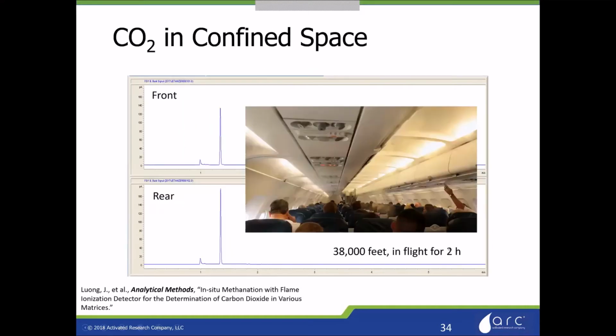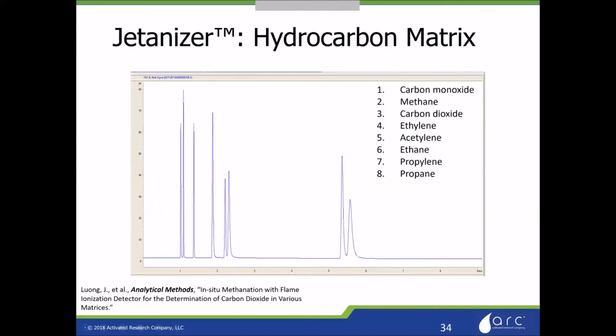And I will mention about the backflush, there is a little bit of back pressure from the Jetanizer, and you can use that to your advantage to drop the inlet pressure and force flow to go backwards through your column to flush out any heavies. That method was invented and pioneered by Jim Luong at Dow, and we were excited to see that cool application for the Jetanizer.